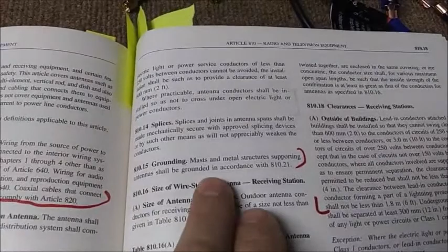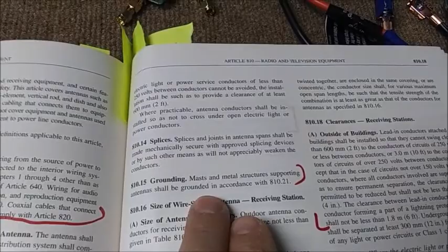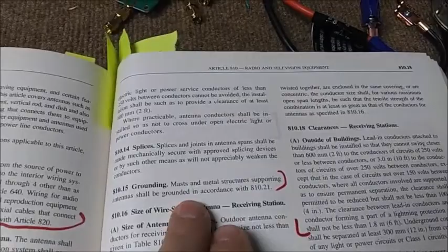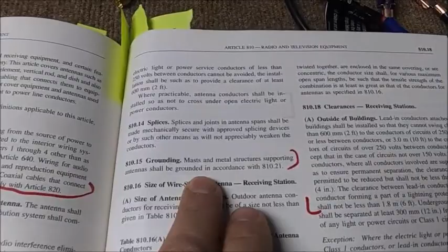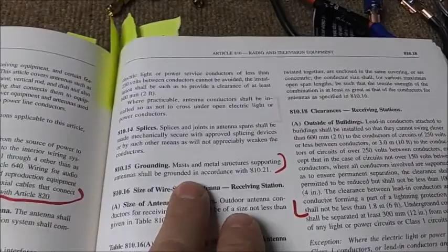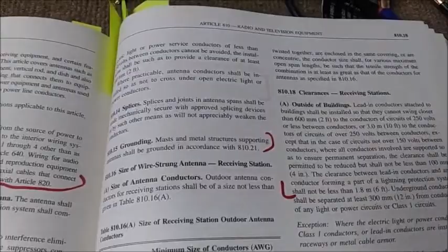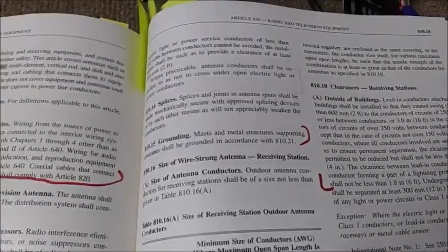810.15, grounding. Masts and metal structures supporting antennas shall be grounded in accordance with 810.21. There are mechanical specifications, there's ground wire sizes, etc. That's fairly obvious. It doesn't say why. It's obvious for lightning discharge. Put up a great big metal pole. It's the elephant in the room. It's going to, so to speak, attract lightning. If you recall the 6-foot spacing requirement, and that's stated as a requirement further on. The previous statement was where practical, but the next statement is a requirement. Put 8-foot pipes in concrete. Put a 100-foot tower on top of the pipes.